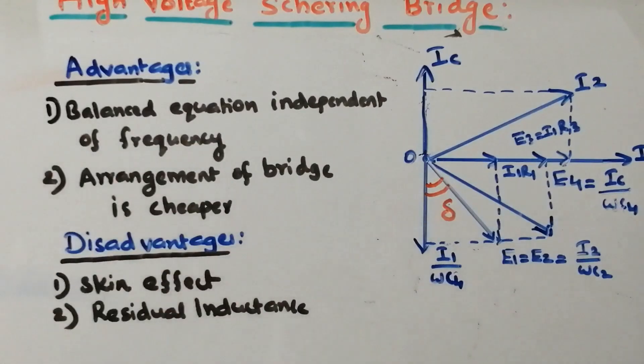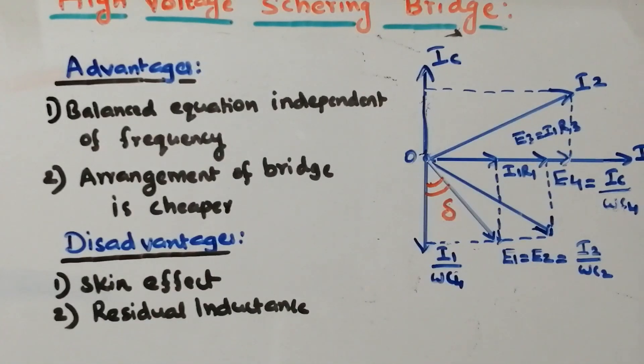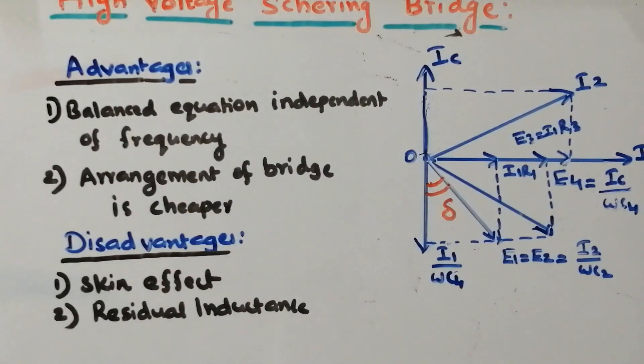When I talk about drawbacks: the skin effect is a major disadvantage — it may cause a heating effect, and losses will also increase because it is operating with high voltage AC. Similarly, because of connecting leads, residual inductance will arise. Moreover, parasitic capacitance is also another issue of the Schering bridge, as different connecting leads create residual inductance as well as parasitic capacitance. These are the major pros and cons of high voltage Schering bridge.